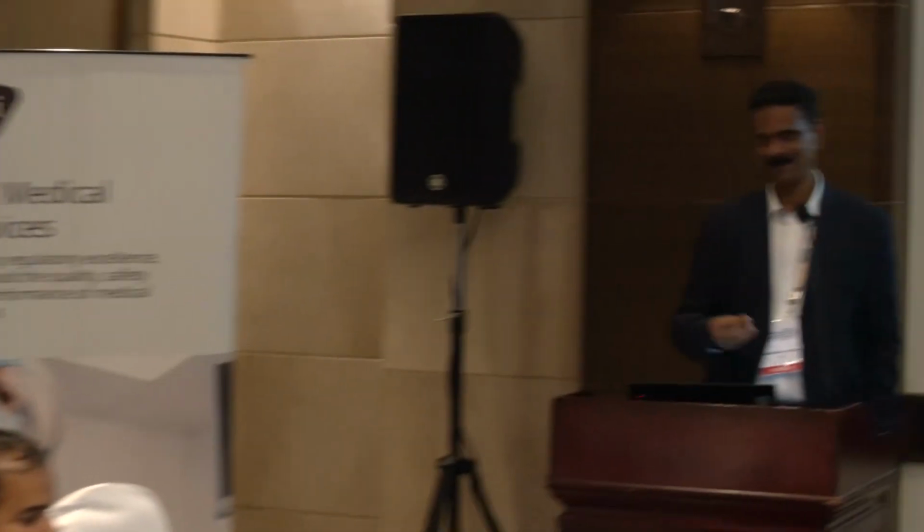No, sorry, to clarify, it's not from PMS, it's from previous literature. Let's say literature till the last CER, and then now in this CER, they are comparing the new data from their own device. From the SOTA analysis itself? No, from their own device data. That's what we know, because again, when we have gone through the state of the art analysis, we have seen benchmark devices, similar devices, how they perform in the market. So we want that data. So it is not from your own data, I mean the manufacturer's own data, which I think is biased.